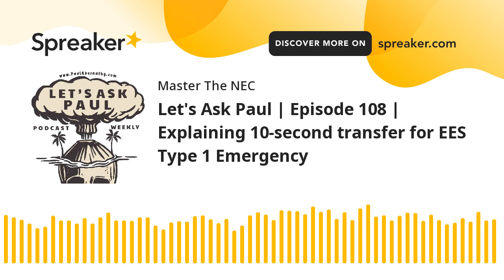Now, remember, even a generator is going to be able to handle other loads other than just emergency, right? And we have a thought of different types of things like emergency, legally required, and then optional. Depending on the hospital, the number of transfer switches that you have is going to be dependent on the KVA that is calculated for that hospital. So again, I'm not going to go into that lesson today, but you're going to have to work with the AHJ and the hospital administrator in order to determine that level. But it didn't sound like you were asking for the number of transfer switches. You just wanted to know whether or not it had the generator and the transfer switch.